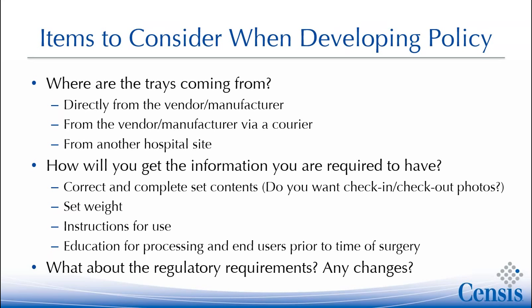Instructions for use from the manufacturer, please remember, I have had vendors come in that evening and say, oh, I forgot to bring in the instructions for use, but this is how you do it. That's when you look at them and say, well, this is how we do it. If we don't have written instructions for use, then we can't sterilize your trays. You will find that this is the best medicine for those instances when you run into a vendor that doesn't provide instructions for use.